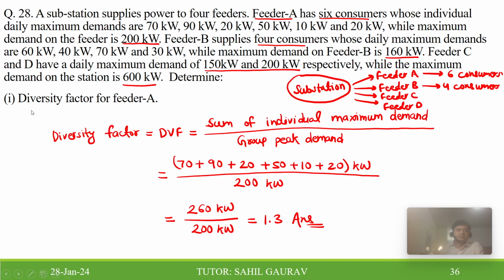So the first problem is the diversity factor for feeder A. We know the diversity factor is the sum of individual maximum demands divided by the group peak demand. Feeder A has 6 consumers and all the peak demands are given: 70 plus 90 plus 20 plus 50 plus 10 plus 20. This feeder's maximum demand is also given, that is the group peak demand, so we divide by 200 kilowatt. It will give you the answer 1.3. If you have any doubt, you can ask.